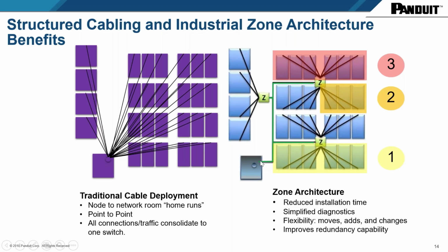Therefore, you would need maybe a zone 1 or a level 1 MICE for this green cabling going to different zones because they happen to be running in a ceiling environment. And inside the cell, you will then have to worry about the MICE rating. That makes it a very efficient way of distributing the network.